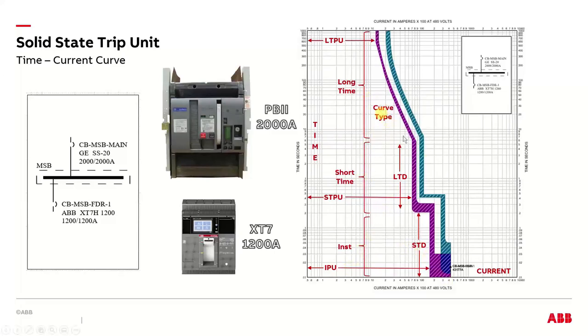So you go into your EasyPower, you produce the curve, you produce the breaker that you want, and then you make all these adjustments so that the breaker fits the performance that you want, and then also coordinates with another breaker. So the purple is your smaller breaker, say 100 amps, and then your blue is a larger breaker, say 250, and you can see that if it had a 900 amp fault, the purple will trip before the blue does anything. So these breakers are coordinated.